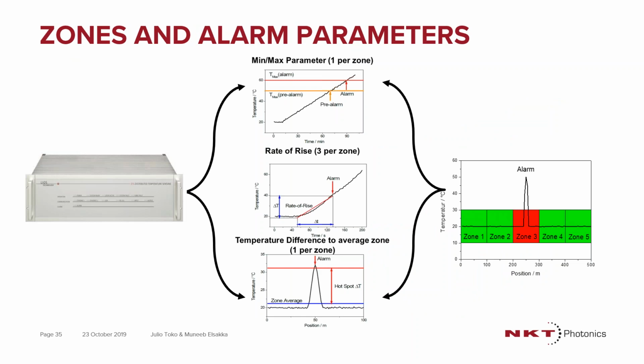The same cable can also be broken down into zones and alarms. So for each section, you can say, this section I'm working towards, let's say, a switchgear room, I'm going to change the alarm parameters. Each zone can have 3 rate of rise values. You can do maximum temperature alarming, and you can do a hotspot. So within the same room, if you see a temperature that is maybe 10 degrees above the average temperature, that means at that given location there is an event happening from a thermal point of view, there's a heat source that needs to be investigated.